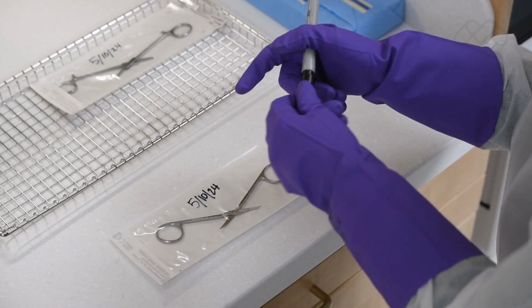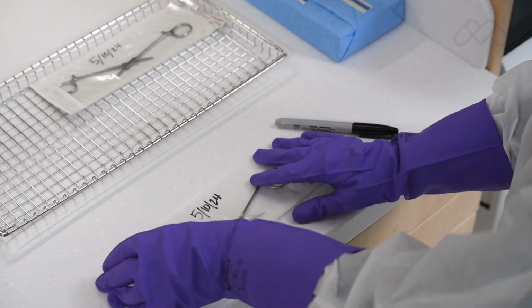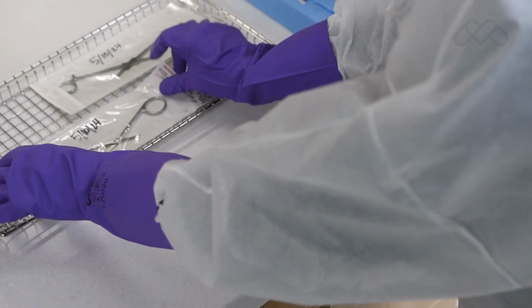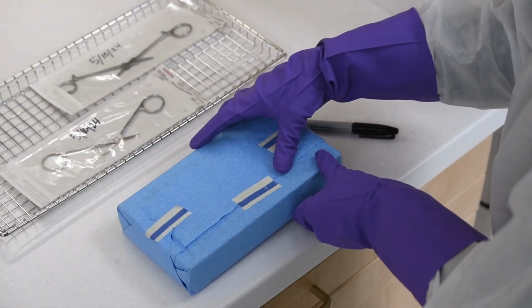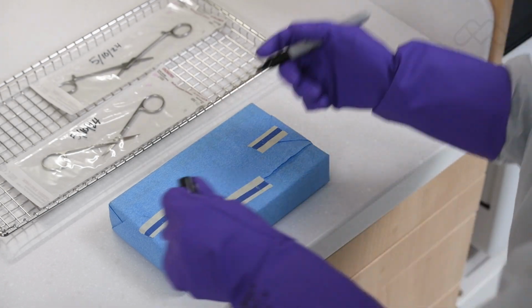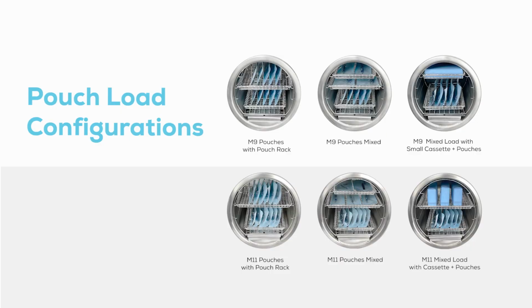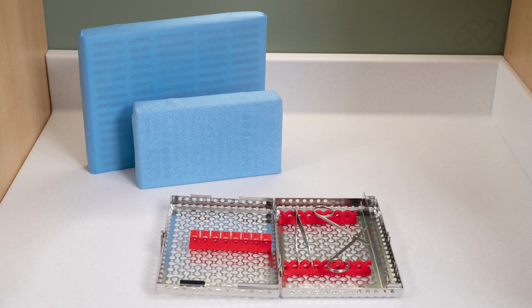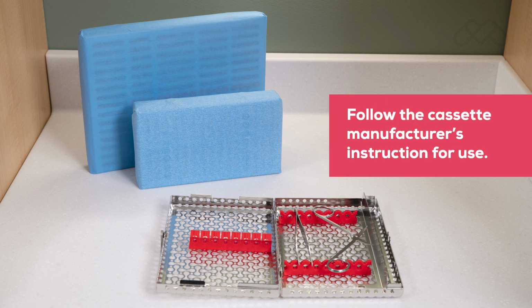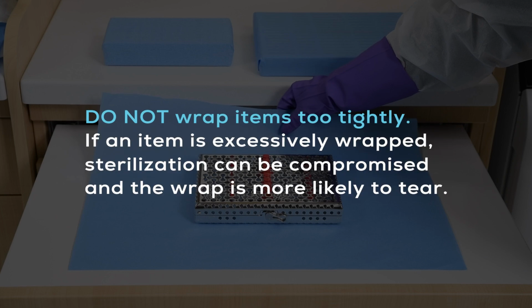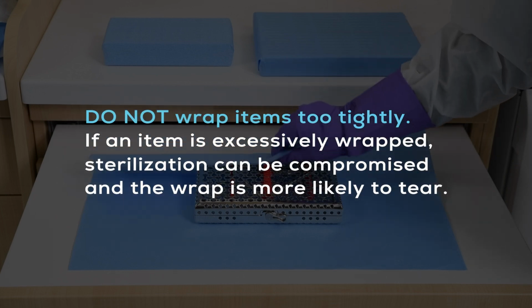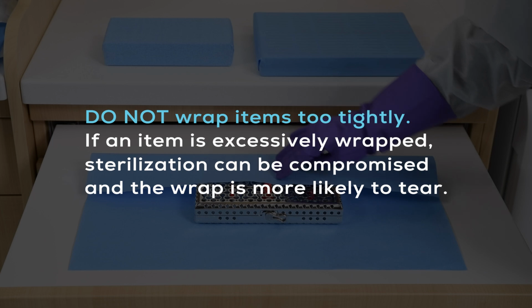On paper and plastic pouches, only mark on the plastic side of the pouch. On wrapped packs, mark the labeling information on the indicator tape or apply a separate label. Shown here are some recommended pouch load configurations for Midmark steam sterilizers. When using cassettes in the M9 and M11, follow the cassette manufacturer's instructions for use. Do not wrap items too tightly. If an item is excessively wrapped, sterilization can be compromised and the wrap is more likely to tear.